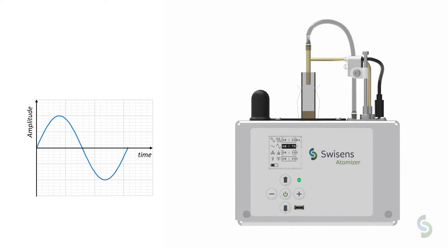The particles suspended in the cuvette are then transported out by a weak airflow generated by the integrated blower. The generated aerosol particles are then sucked away by an external airflow — this might be a connected measurement device or any other application. The aerosolization process can easily be controlled by the control panel. Various types of particles with different shapes, masses, and sizes react differently to the vibration frequency, so the vibration frequency can be tuned by the operator to support aerosolization of all kinds of particles.